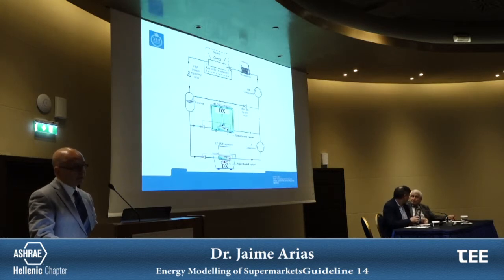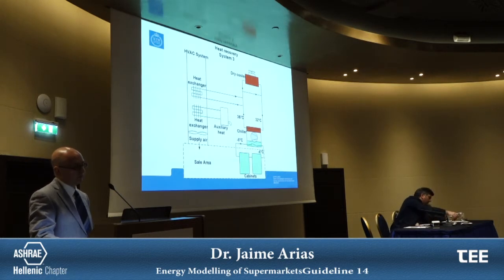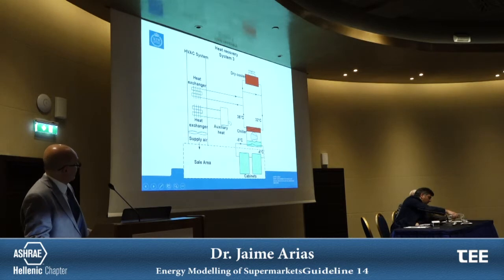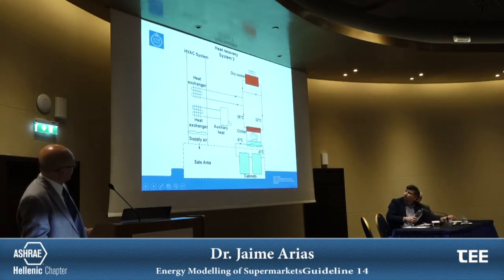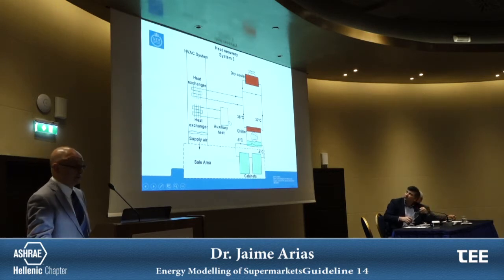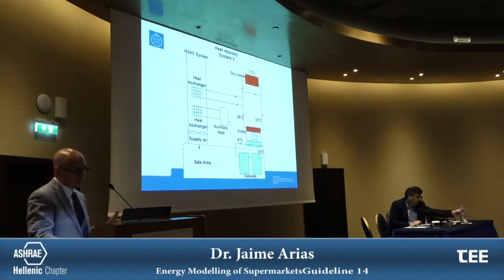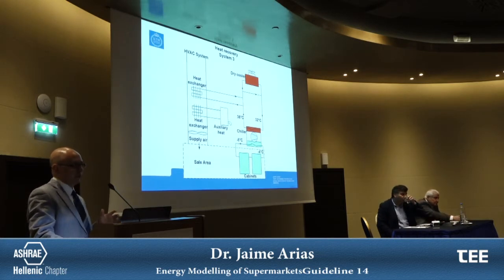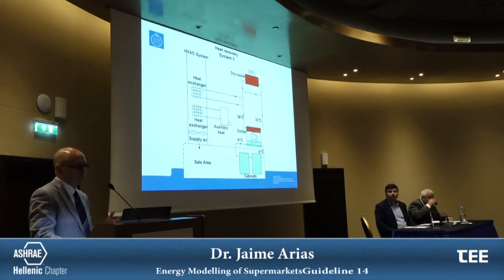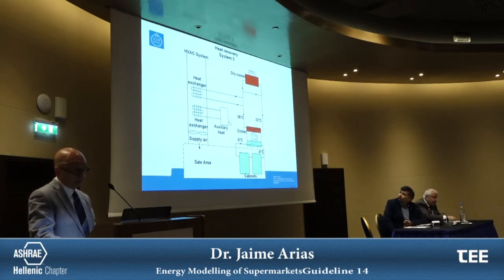I will say some words about the heat recovery system when we implement this one. This is the main idea. It is the same chiller and the same temperature as I mentioned before to the cabinet, -8, -4. And we have a temperature of 36, that is to the heat exchanger connected with the HVAC system. And after that we have an auxiliary heating, if the heat from the condenser is not enough to cover the heating demand in the system. When we started with the heat recovery system, we found a lot of problems with mixing of fluid, and sometimes with low heating from the refrigeration system.